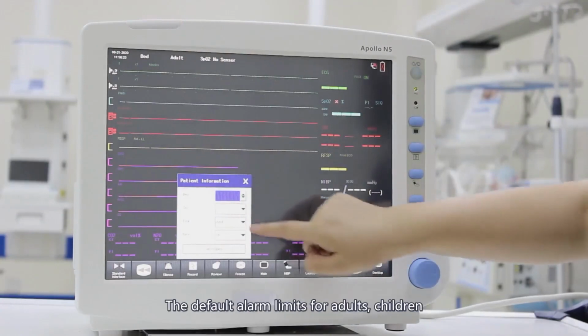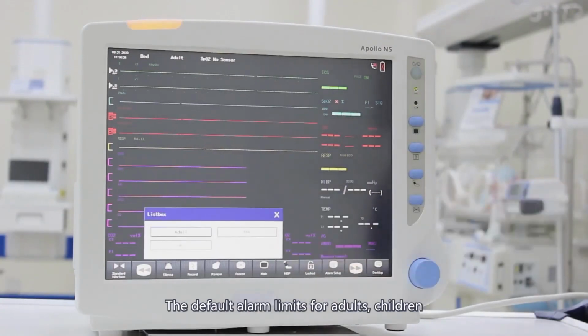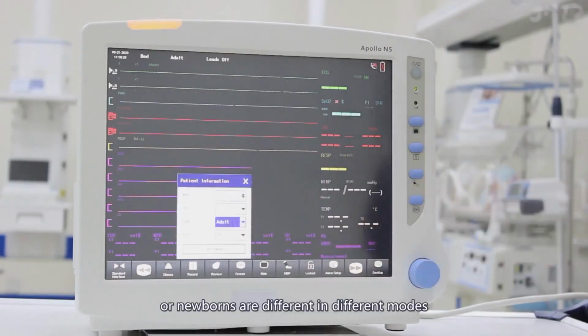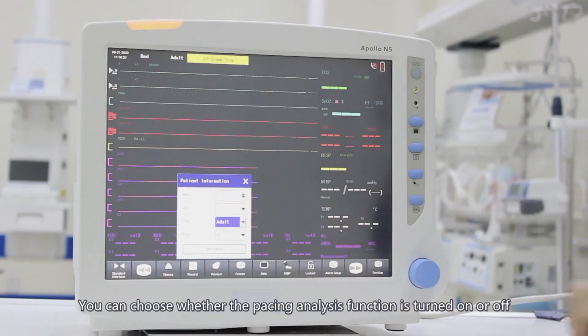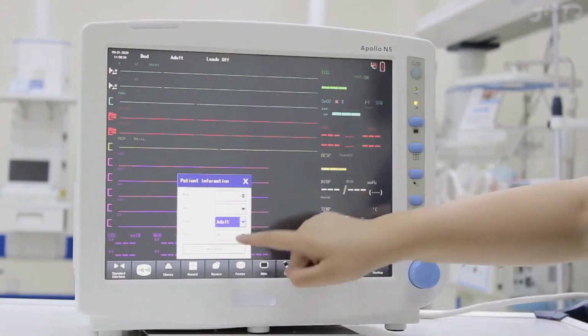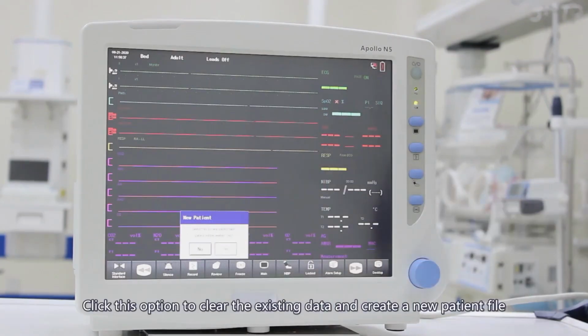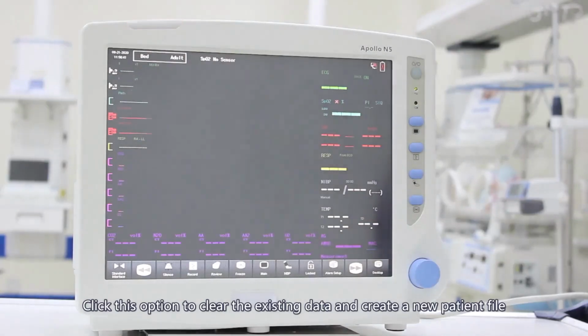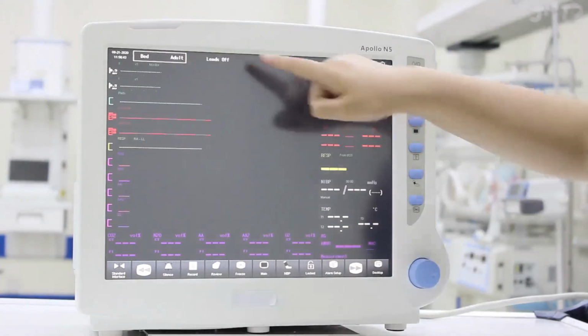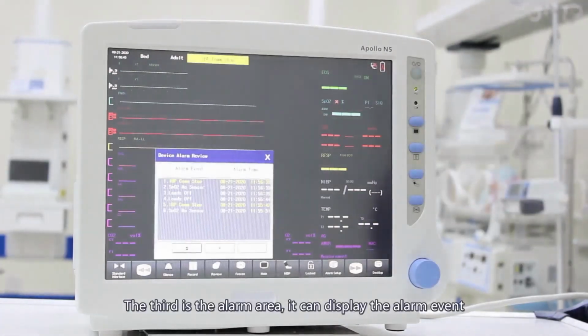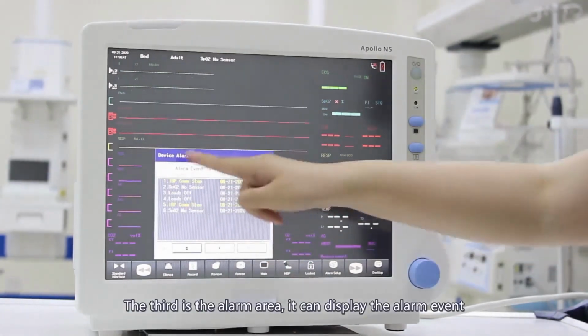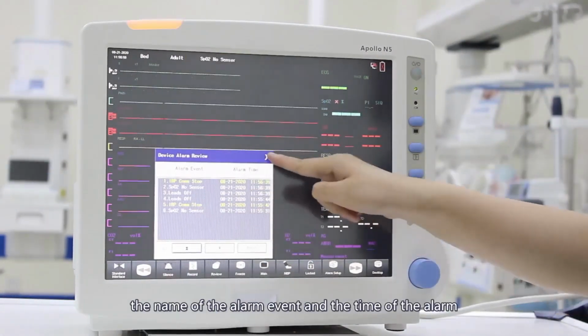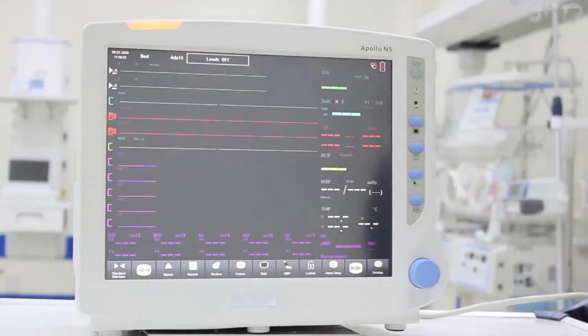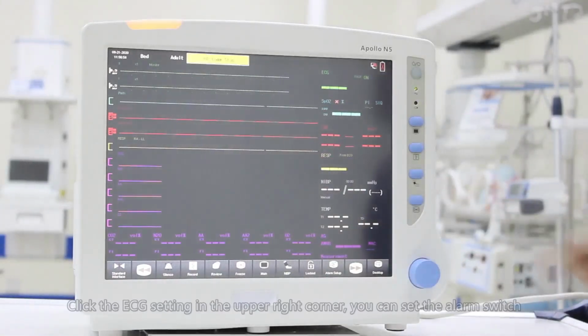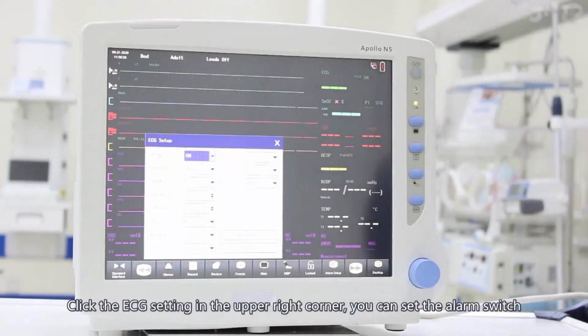The default alarm limits for adults, children, or newborns are different in different modes. You can choose whether the pacing analysis function is turned on or off. Click this option to clear the existing data and create a new patient file. The third is the alarm area. It can display the alarm event, the name of the alarm event, and the time of the alarm. Click the ECG setting in the upper right corner.